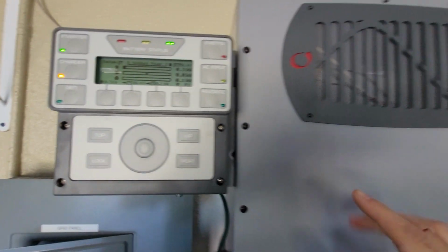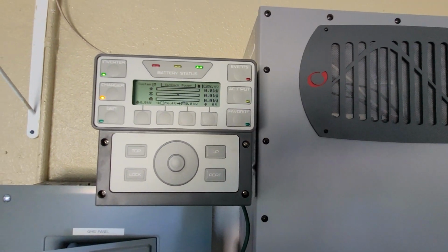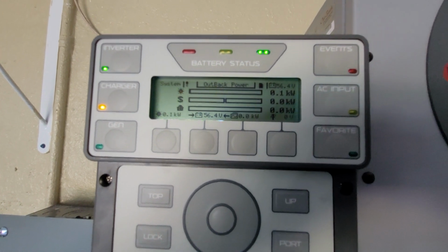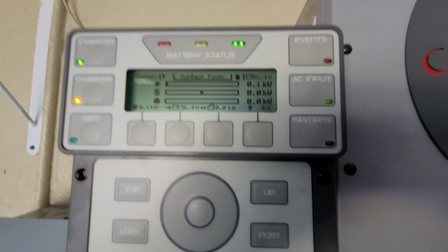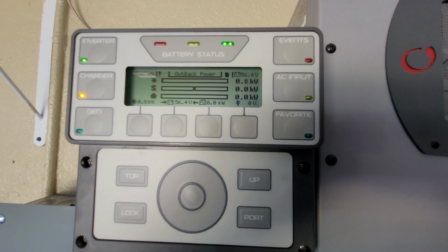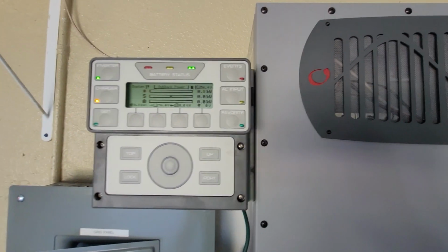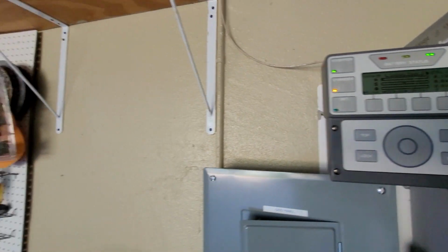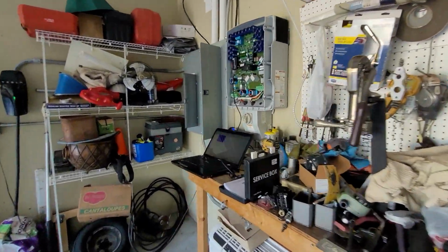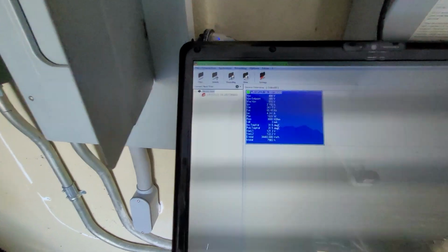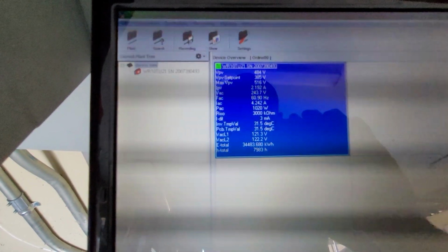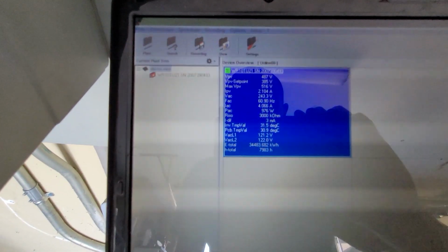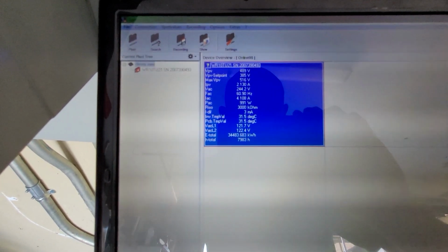Because what this will do is these inverters will shift the frequency to tell the grid tie inverter over there to pick up the load, and it happens pretty quick. But like if an older air conditioner turned on or something, you know, these would pick up the slack. But he's got a variable speed AC, so that's why it's running right now, and it's probably pulling maybe 700 or 800 watts right now. That's at about 1,000. And so this is basically what it'll look like when you properly change the settings on an AC coupled system.